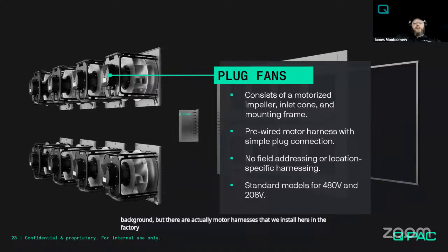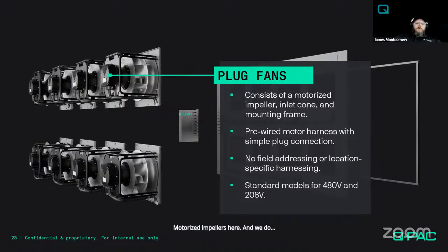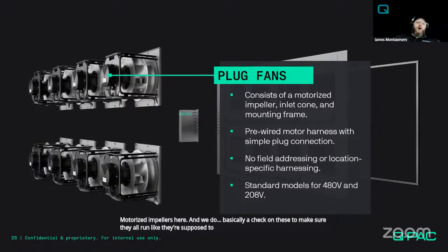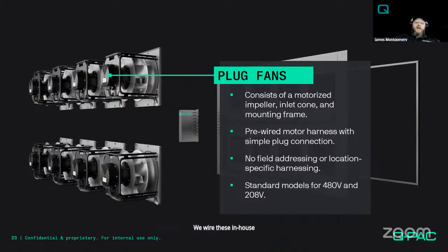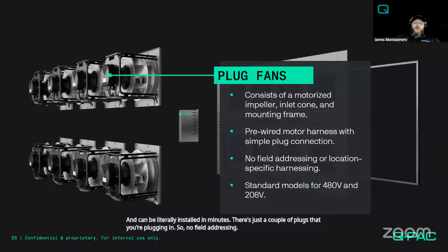So we take these motorized impellers here and we do basically a check on these to make sure they all run like they're supposed to, so we can cut failures down to almost nothing. We wire these in-house and make these harnesses. That way, if there ever is a failure out in the field, one of these can be shipped out and can be literally installed in minutes. There's just a couple of plugs that you're plugging in. So no field addressing, no location specific harnessing.